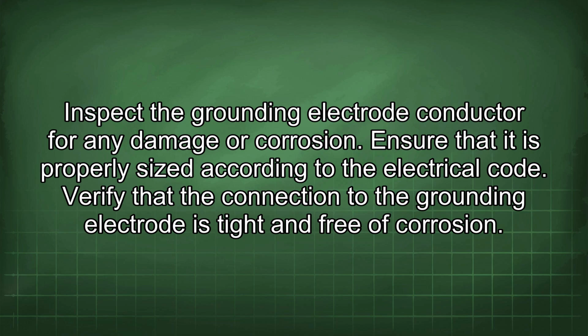Inspect the grounding electrode conductor for any damage or corrosion. Ensure that it is properly sized according to the electrical code. Verify that the connection to the grounding electrode is tight and free of corrosion.